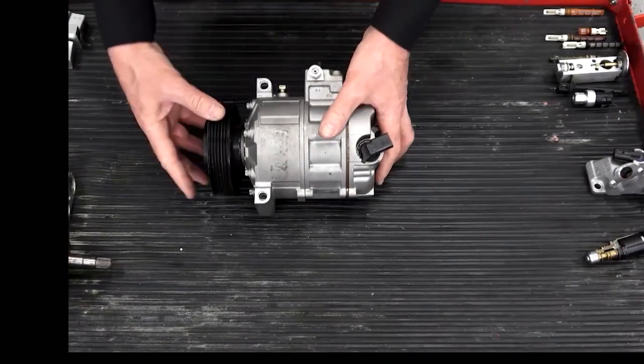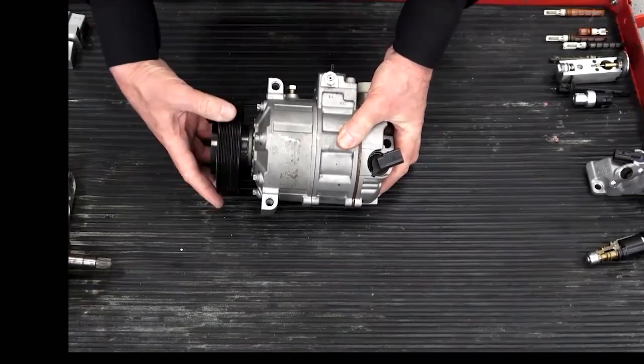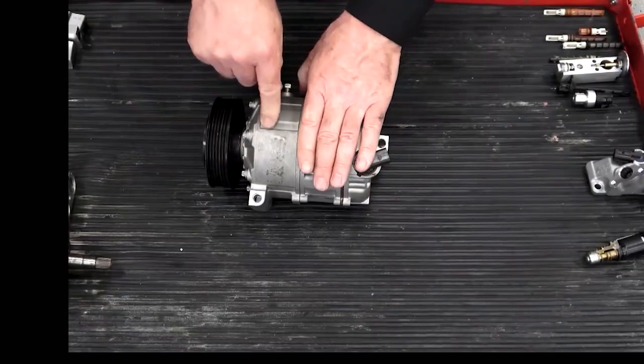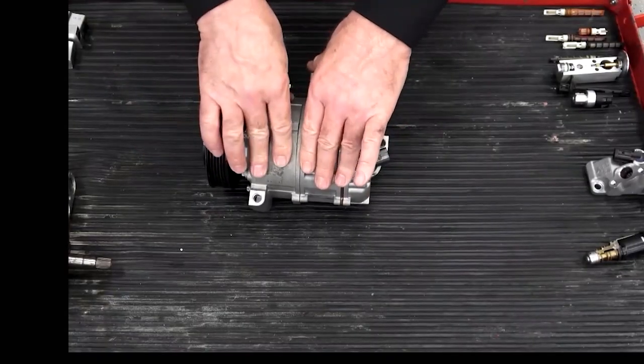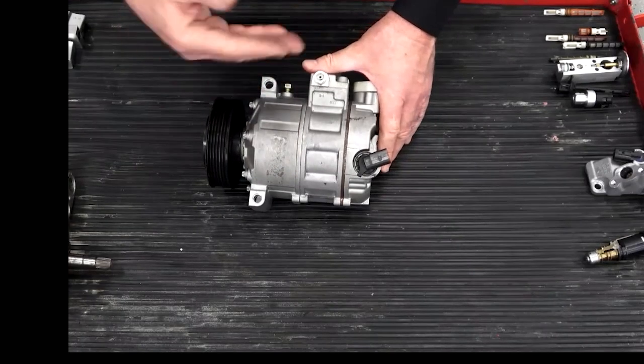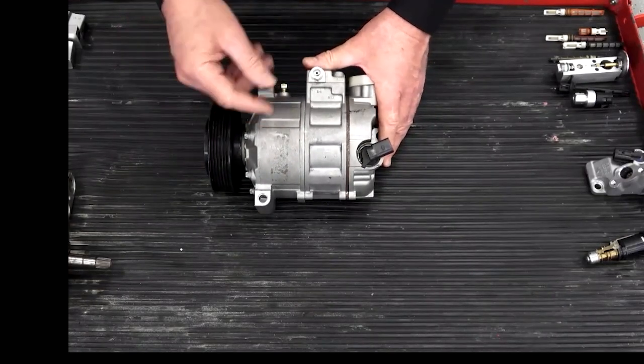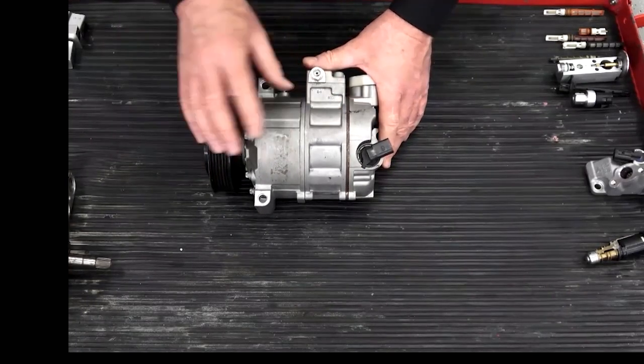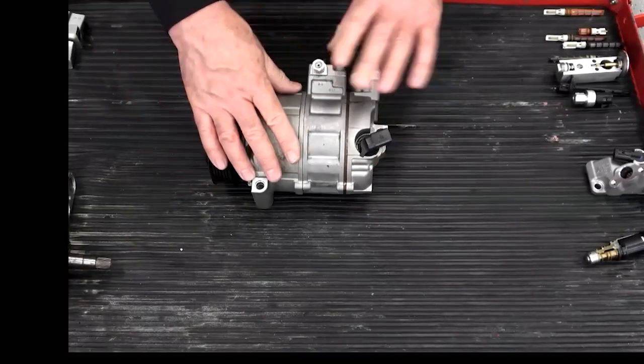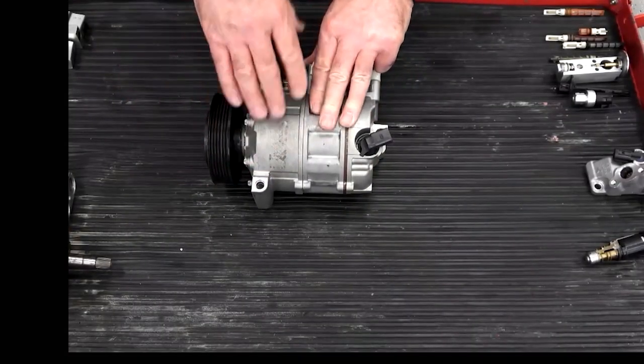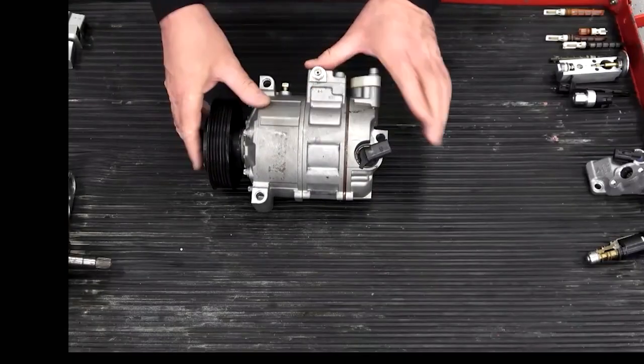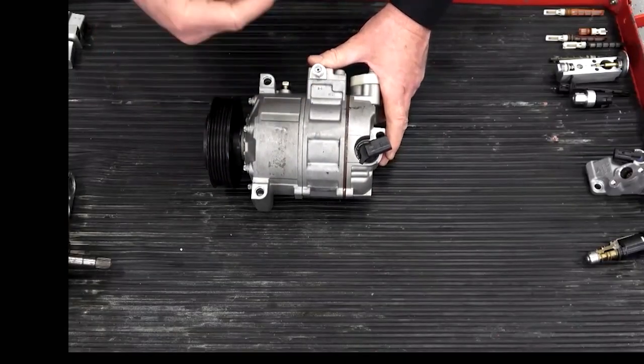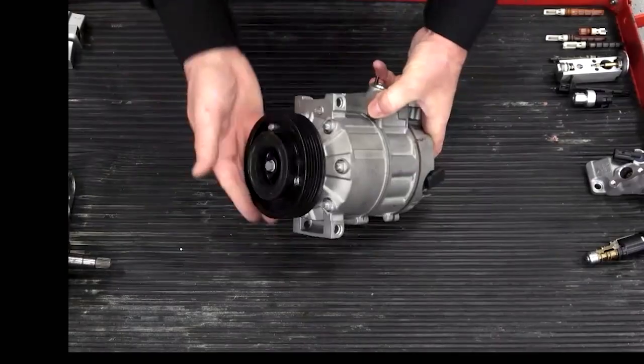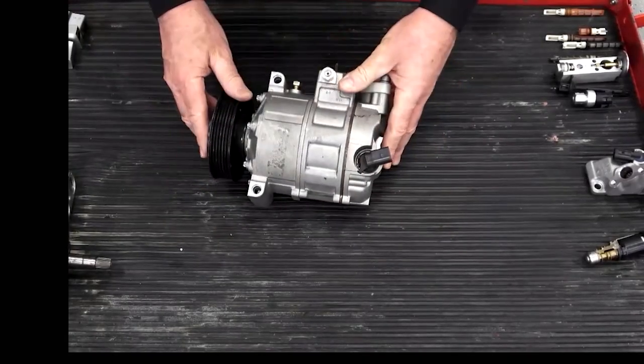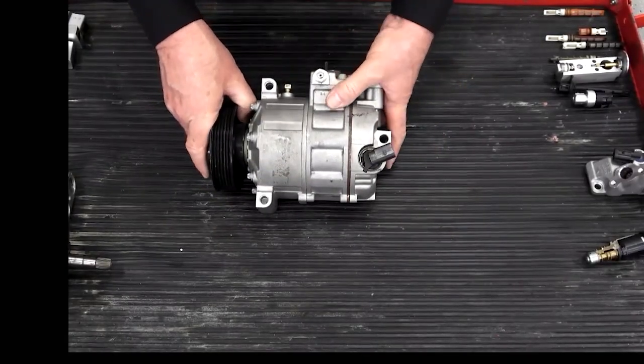And that's because if you run this compressor, even just around the block, even though there's oil inside, you need refrigerant in the system to keep the oil stirred up, to keep the oil agitated, and to keep all the moving parts lubricated. You never want to run this compressor with no refrigerant in the system. Otherwise, I've seen many of them seized and damaged very easily because the compressor was run. Once you start the engine, the shaft is turning. If you run it without refrigerant, you're potentially going to ruin the compressor inside. So just FYI.